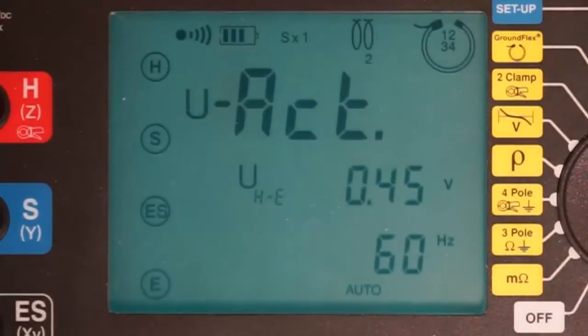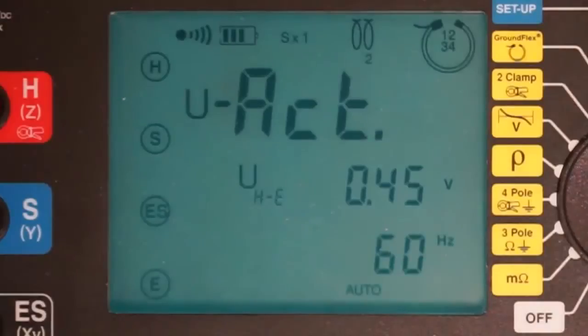Pressing the display button again shows the voltage between the green E output terminal and the electrode connected to the instrument via the red H connector. This voltage, labeled U sub HE, should be within a volt of the U sub SES voltage, as is the case here. This indicates that both electrodes are placed far enough away from the tower so that they are not affected by the tower leg's potential shells of influence.